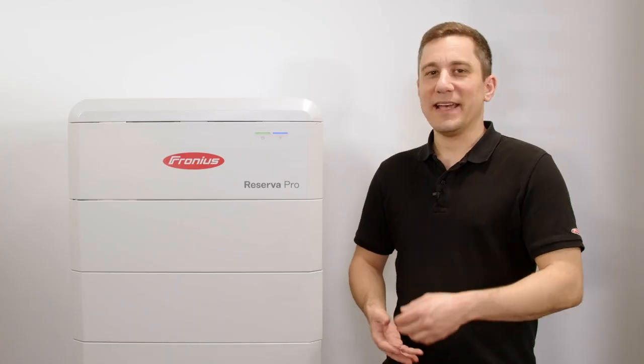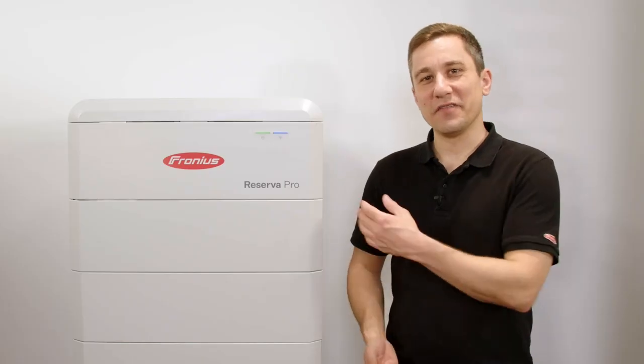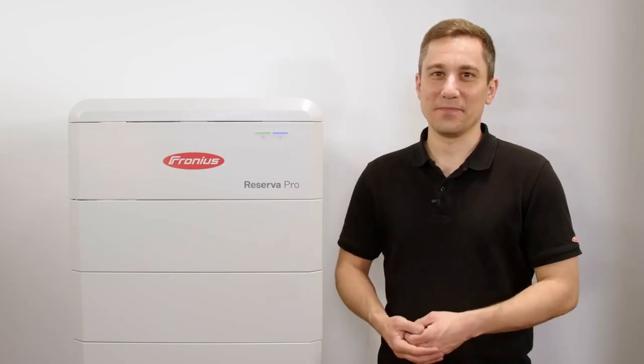Same thing goes for the inverter firmware. Please check before the commissioning process that your inverter has the newest firmware installed, especially when you are updating an older inverter, like 2 or 3 years old. Please make sure that the newest firmware is installed so that you can add the Fronius battery to the system. And with that, installation and commissioning of the Fronius Reserva Pro is finished.